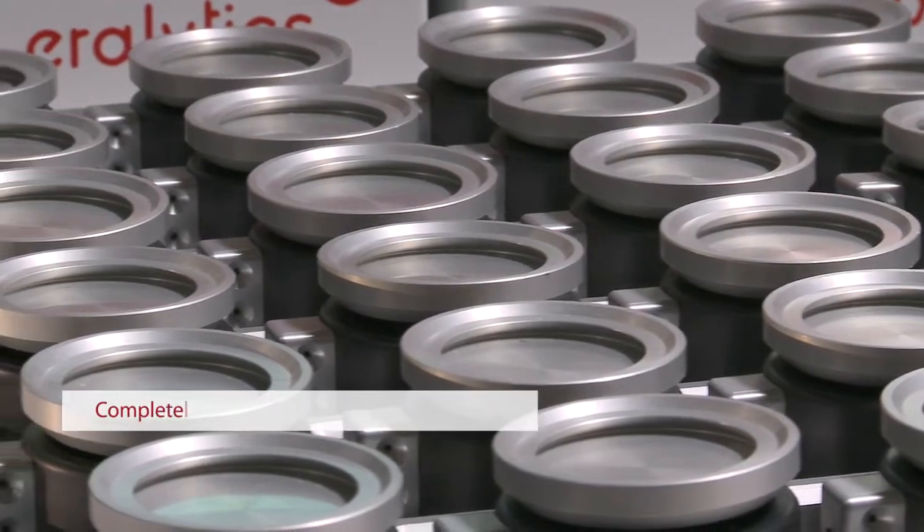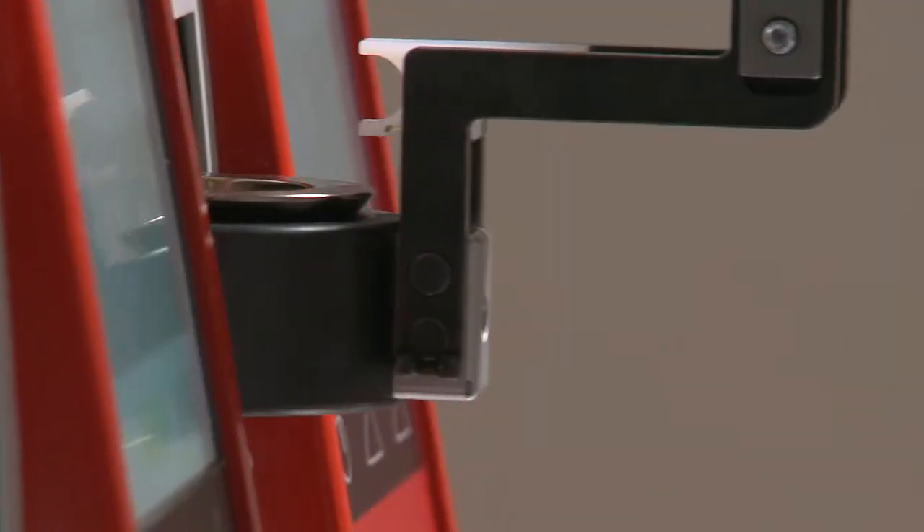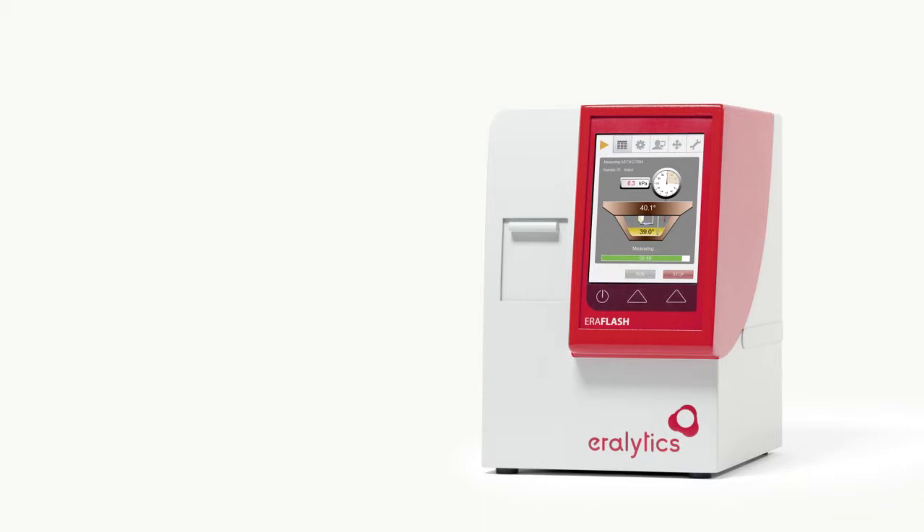Each EraFlash can measure up to 30 samples before the sample cups must be refilled. The measurement procedure is completely unattended, and the safest way of flashpoint testing can now become a 24/7 operation. Ask your country representative for a free trial instrument and let EraFlash convince you of the safe side of flashpoint testing.